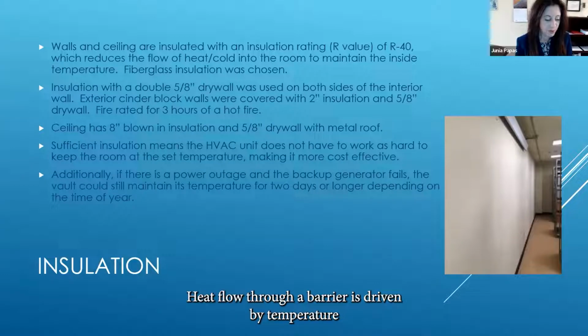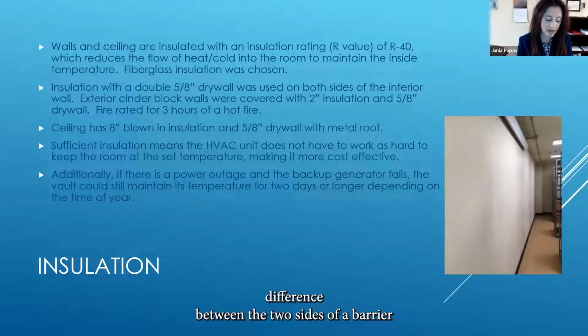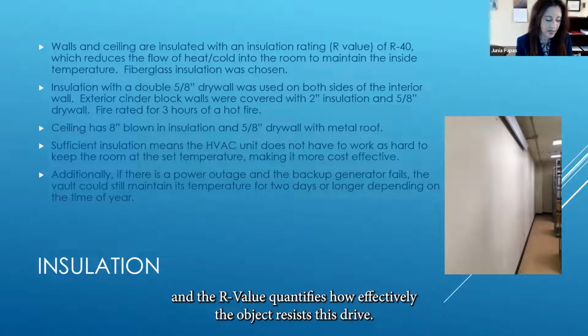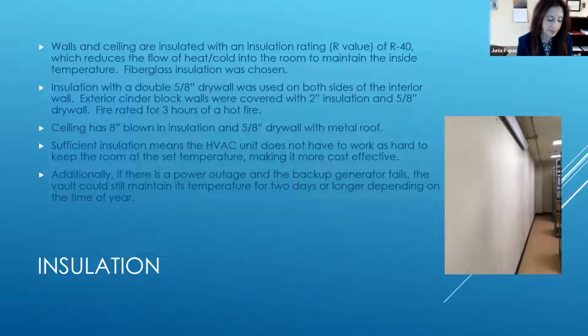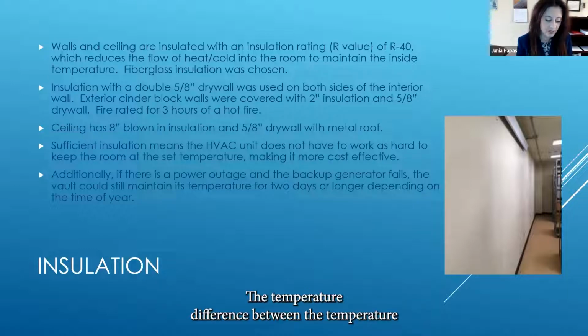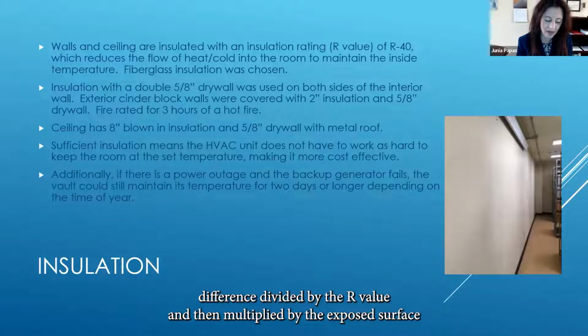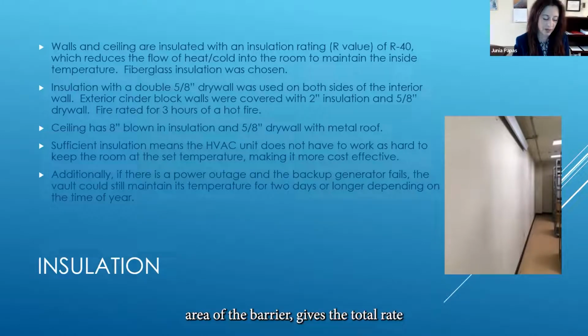Heat flow through a barrier is driven by temperature difference between the two sides of a barrier, and the R value quantifies how effectively the object resists this drive. The temperature difference divided by the R value and then multiplied by the exposed surface area of the barrier gives the total rate of heat flow through the barrier.